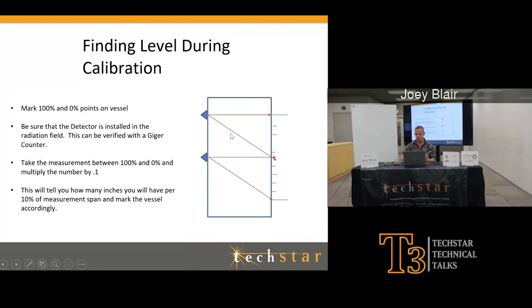So on this diagram here, you can see my pointer. If every one of these hash marks were 10%, and I wanted to take a calibration point at 10%, I would take this to the vessel right next to my detector, right around my 10% point, and start filling it so that I'm at 10%. Whenever I suddenly see high radiation, let's say it's at 700 microrem, and then suddenly I see it drop to 20 microrem, that just tells me my process fluid just filled up past that point. Operation stop, filling. Let me take a calibration point here, and you can do that throughout the measurement.